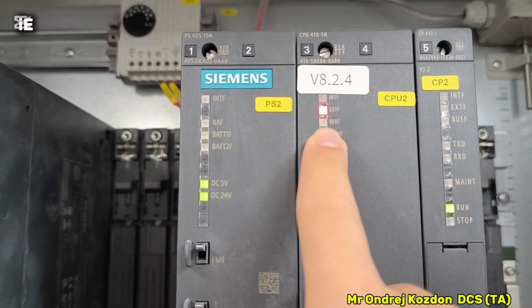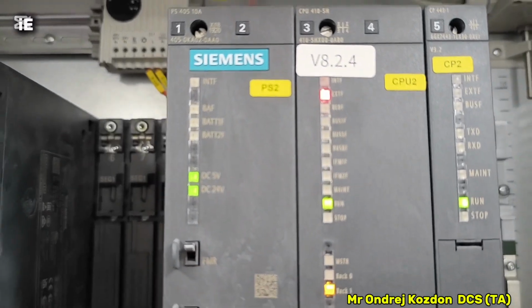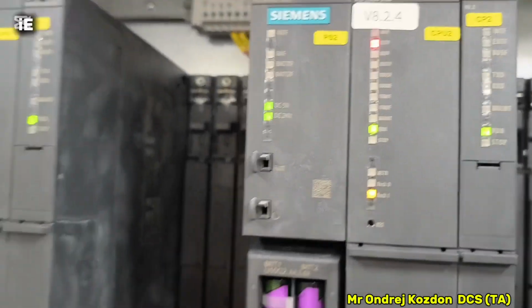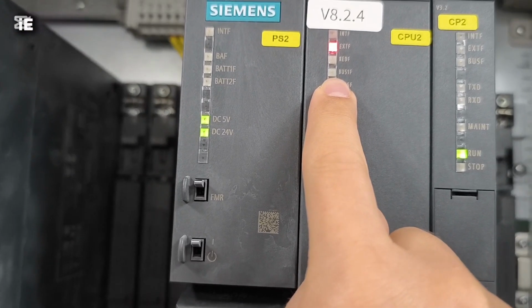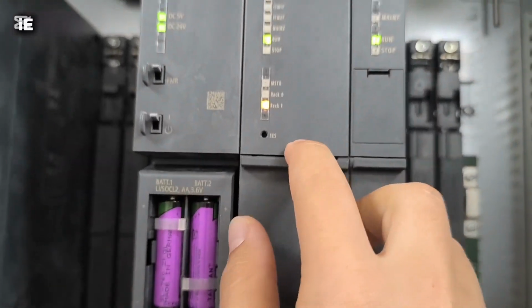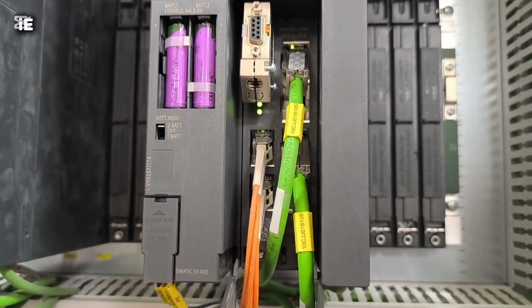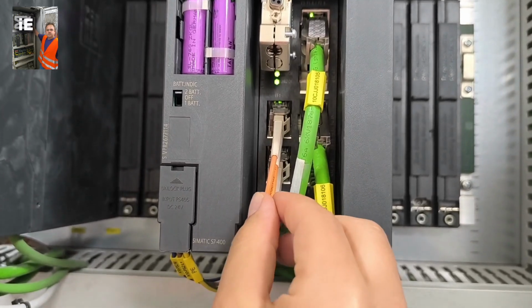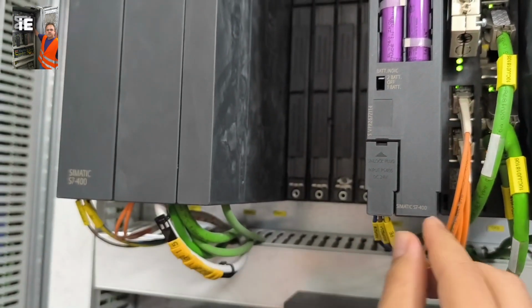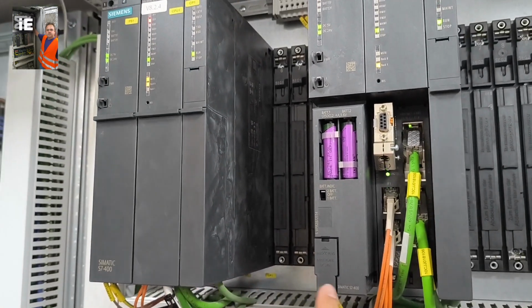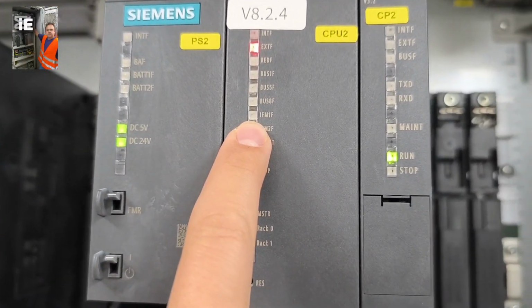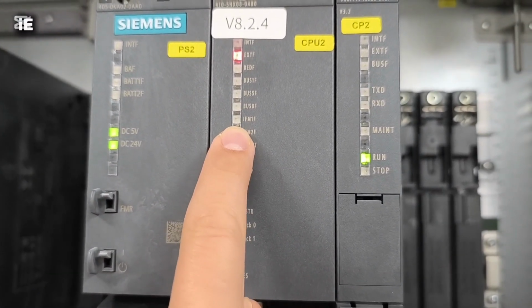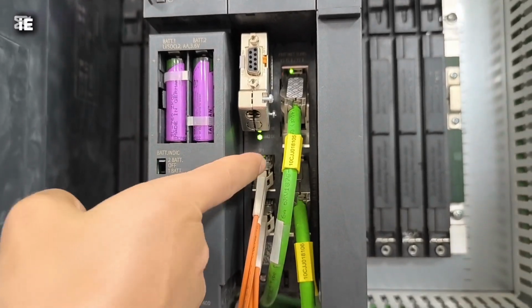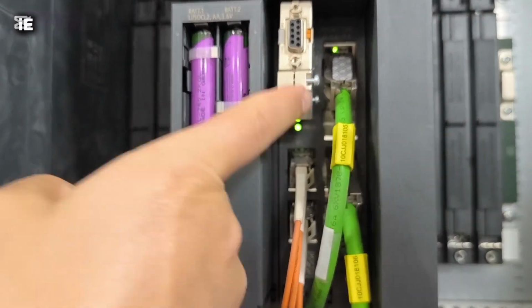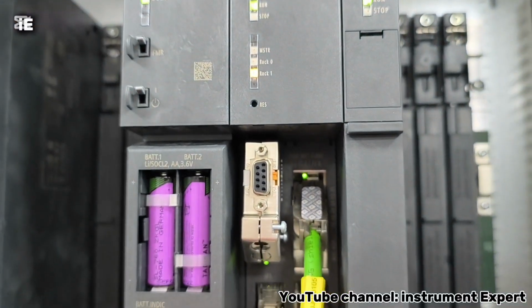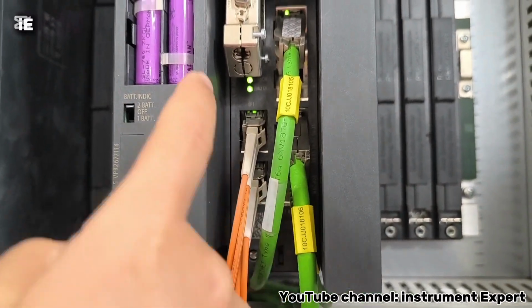Here we have redundancy fail because we have two PLC in redundant configuration. Here we have bus fail number 1. Bus fail number 1 is bus for the optics. It means for synchronizing data between these two PLC in the redundant mode. IFM1 means interface module for synchronization between PLC. IFM1 is the first one optics, and IFM2 is the second optics, the bottom.